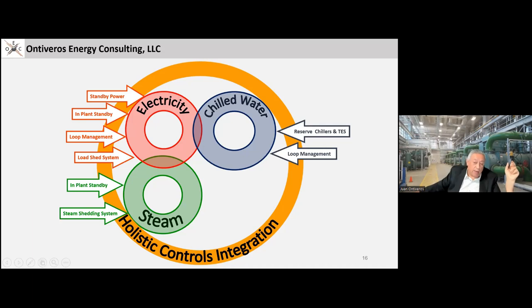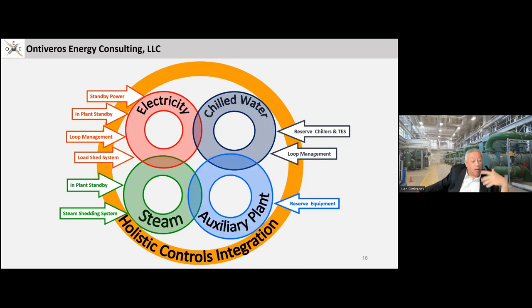For chilled water, you have reserve chillers, you have TES. You also have loop management, because you're sending chilled water out to the campus. And for us, chilled water was between 30 and 50% of the total electrical load, so you have to pay a lot of attention to how we did that. And then all the auxiliary plant: the cooling towers and the pumps and the fans and everything else supporting all the equipment that's running. You want to have plenty of reserve equipment.